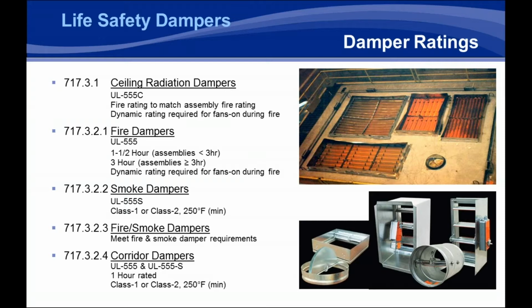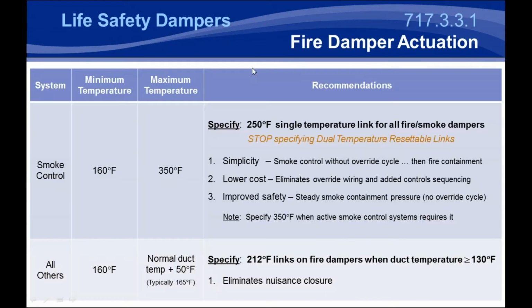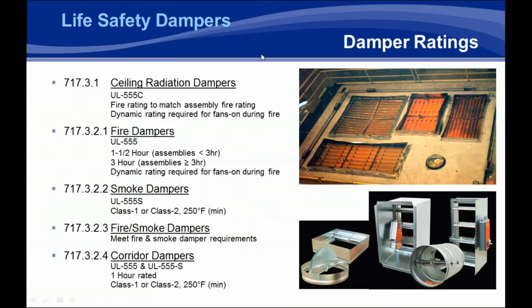The code was silent on the requirement of having a dynamic ceiling damper. It didn't specify static versus dynamic, where static dampers close under no airflow and dynamic dampers close under airflow. So basically all ceiling radiation dampers at that point were static dampers, even though there was this need for them. Because of that, the code adopted the verbiage to allow for a dynamic rated ceiling radiation damper. The problem with that is there is no dynamic rated ceiling radiation damper.